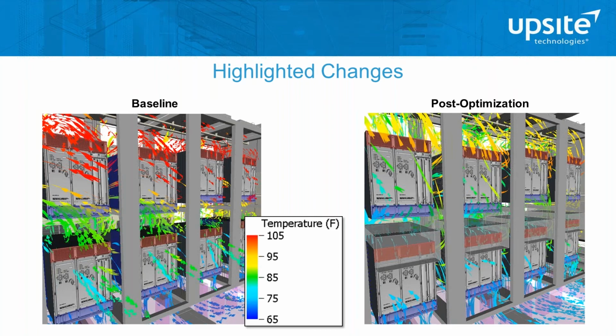To that point, actually, let me highlight one of the cases we've done over the years. We were called into a particularly difficult situation for one of the major banks, where mission critical rooms were at only 45% of IT power load, and they had thermal alarms going off in several cabinets within those data halls. In that case, it was the facility manager who was actually following all the rules exactly as he was deemed to do. He was delivering the cold aisle air at the right temperature, everything was abided by in front of the cabinets, and he was delivering the power and the cooling to where he had to.